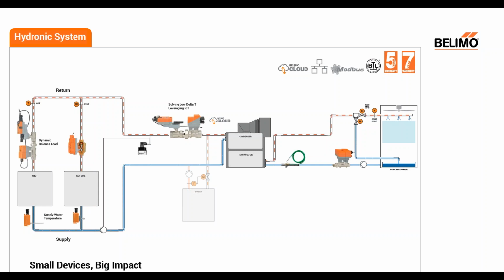In a hydronic system, problems are revealed when buildings' occupants report a comfort issue or facilities see an increase in energy consumption. Common indicators of a hydronic problem are a space that is too hot in one area or too cold in another, poor system delta T, higher than expected energy costs, or even a difficult initial startup.